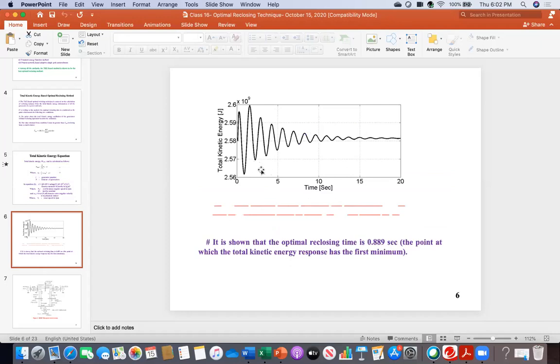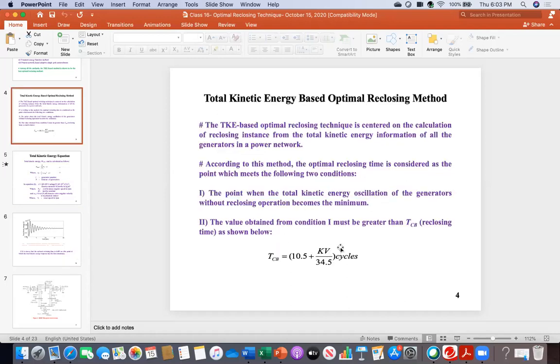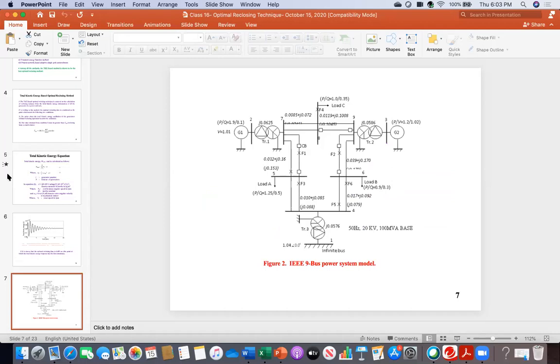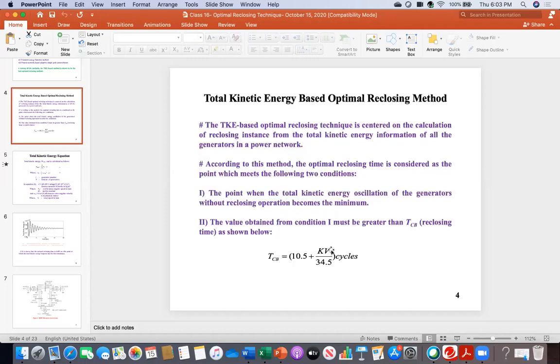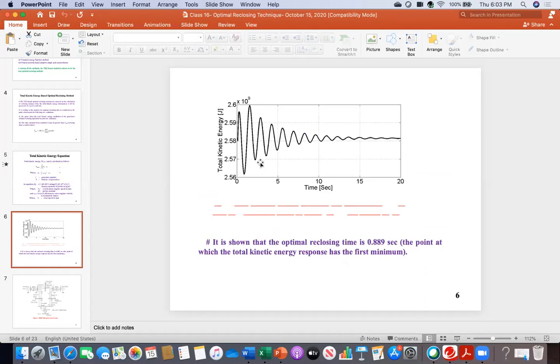That is the rule. I myself have done simulations for various systems, not just this one. You may need to go up to the third point for comparison, depending on the system. Here I calculated based on a 20 kV system. If the voltage is higher, say 500 kV, definitely the result will be larger, and the first point won't be enough, you'll have to go to the second or third point. I have not seen a need to go beyond the third point, typically the first or second point works.